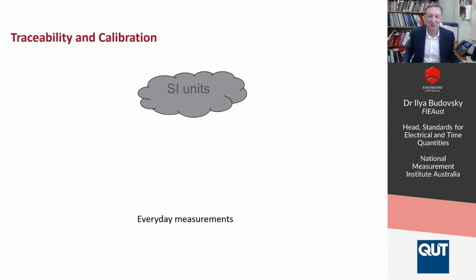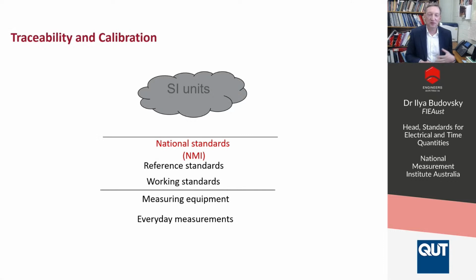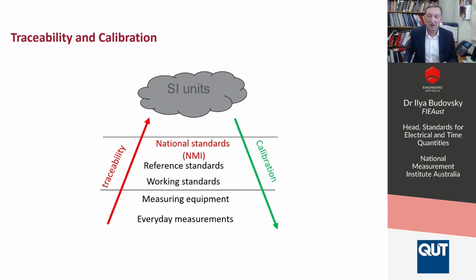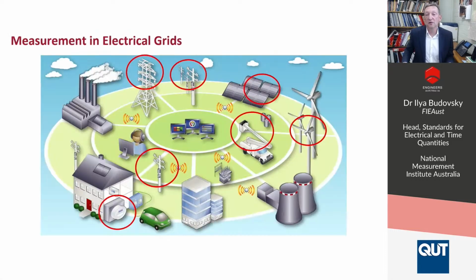What is traceability and calibration? It's linking everyday measurements that are important to the units of the International System of Units, SI. There is usually a pyramid or hierarchy of measurements that provides this link through an unbroken chain of measurement, each associated with its own uncertainty, and through calibration, through comparison to a reference. What we found when we started working on this project is that this hierarchy doesn't quite exist when it comes to numerous measurements that really matter, that occur in electrical grids.